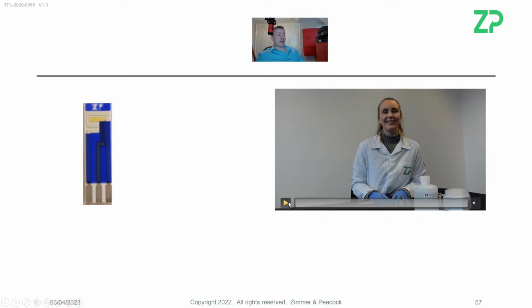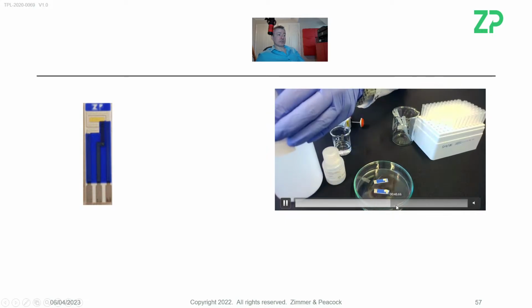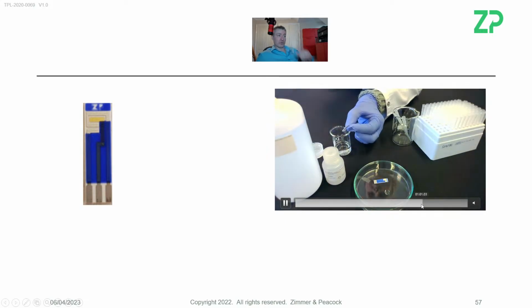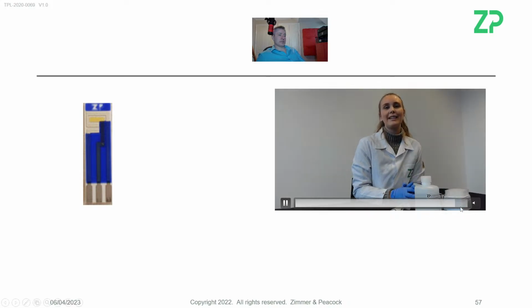And the way you get a nice CV is, if the cyclic voltammogram is looking distorted, then it tells me that the surface is tarnished, and gold is very good at tarnishing. It tarnishes just by, I think, absorbing materials from the atmosphere. So it does need, we kind of call it activating, but you could call it cleaning. And we actually clean the surface just before use. So we do have a cleaning solution for this. If you want to make a homemade cleaning solution, I can't tell you our formulation because it's proprietary, but use some very mild acidic materials, but make it mild.